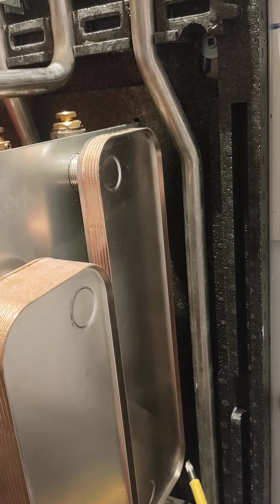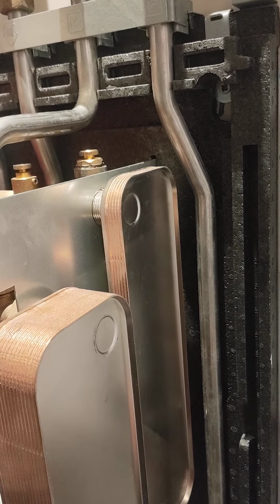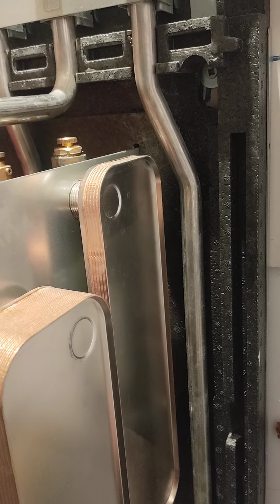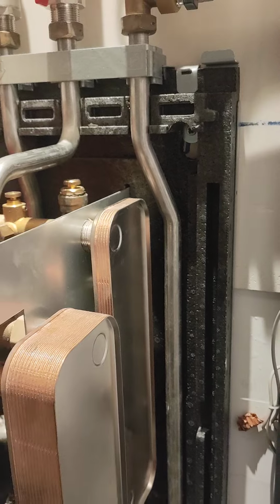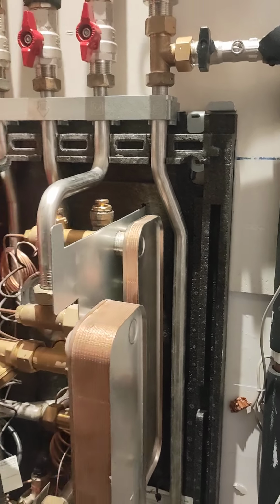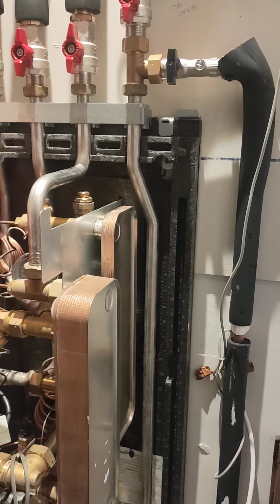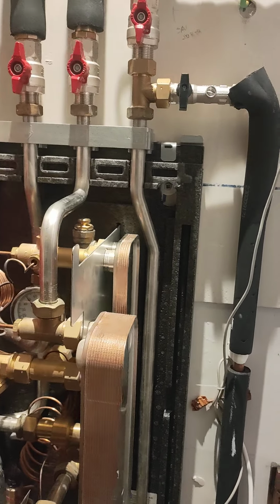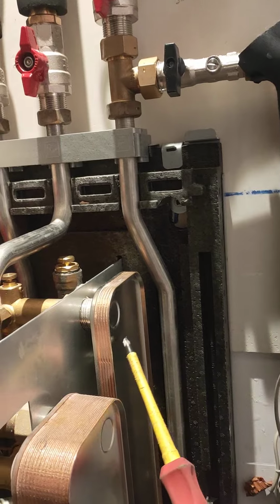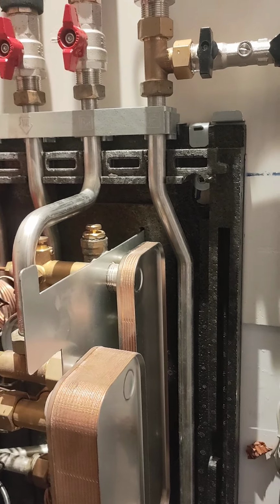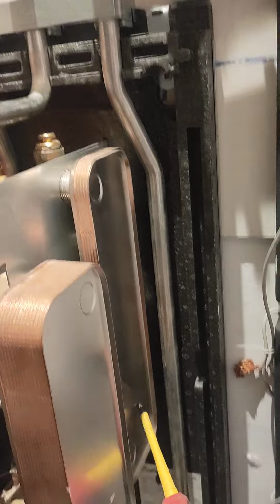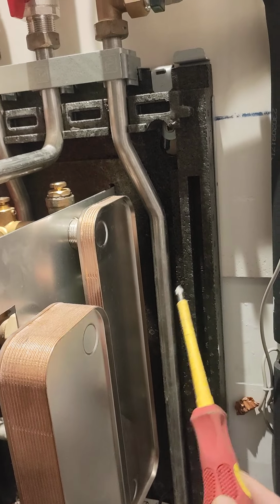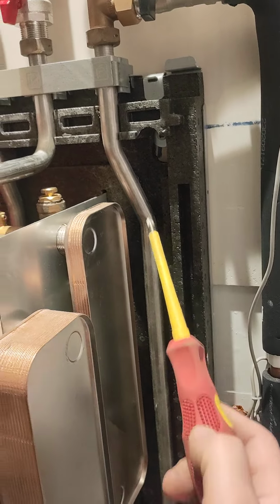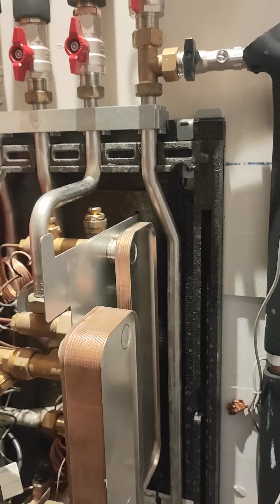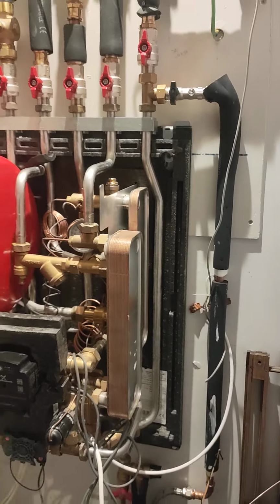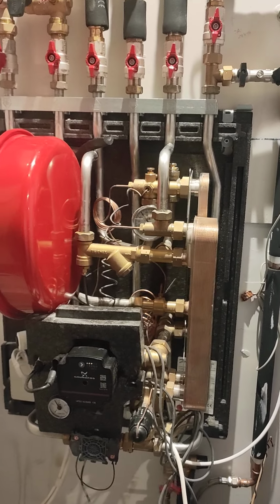Sometimes these get blocked, for example if the system is a bit rusty or it oxidizes, maybe there's a leak somewhere, and fresh water is introduced constantly, which has oxygen. It could create oxidization in the system, and over time, for example in summer, people don't turn their heating on, and then this gets rusty and blocked, so it's very hard to get hold of these plates. You have to clean them with cleaning chemicals.